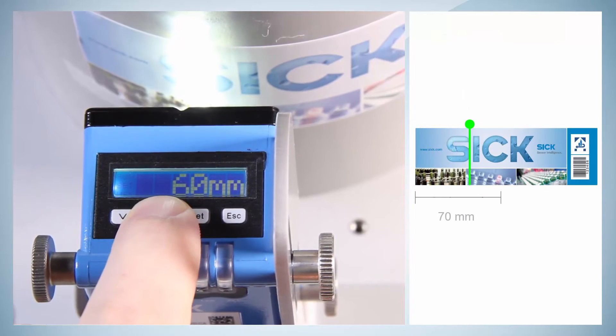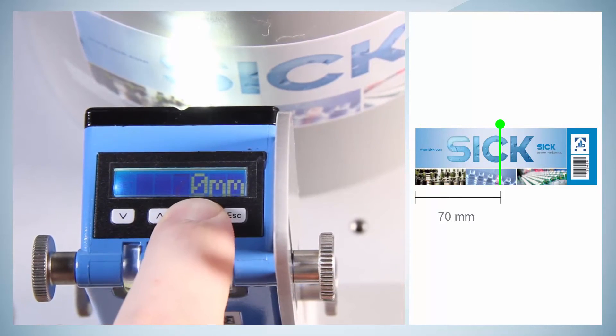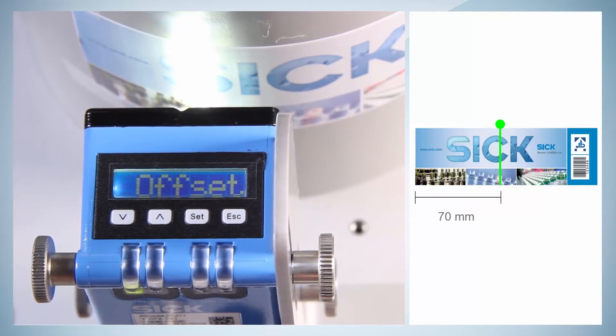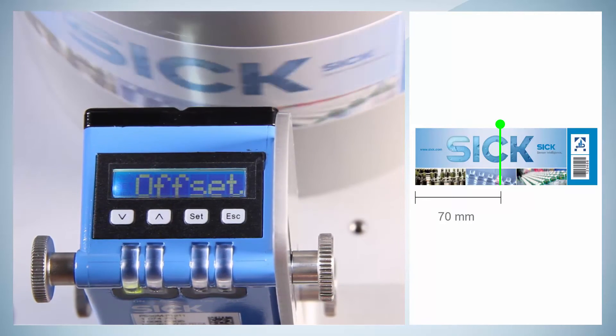As an example, 70 mm is chosen as an offset from the switching point. The setting has to be confirmed by the Set button. The switching point has now been moved successfully by 70 mm.